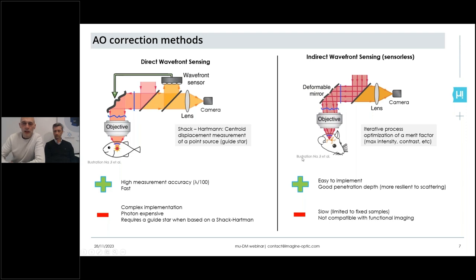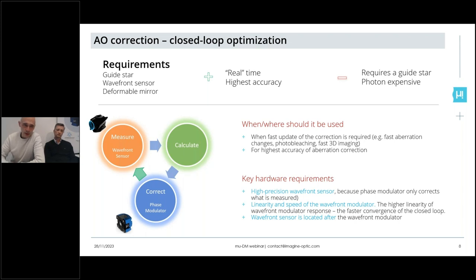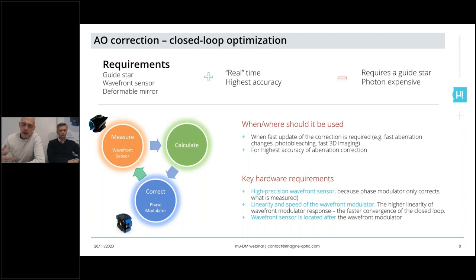For the closed-loop operation, it is usually recommended when a fast update of aberration correction is required — meaning when aberrations are changing over time, for example in ophthalmology or in live imaging of animal models. It is also recommended when you don't want to induce photobleaching due to the adaptive optics process itself, and when fast 3D imaging is required and the corresponding aberrations are changing over the third dimension.